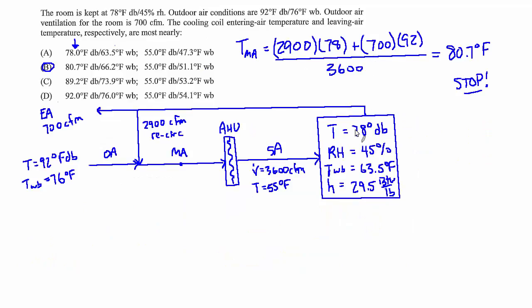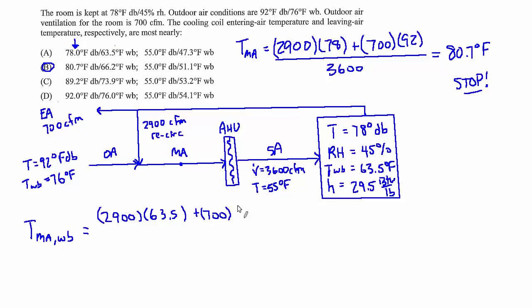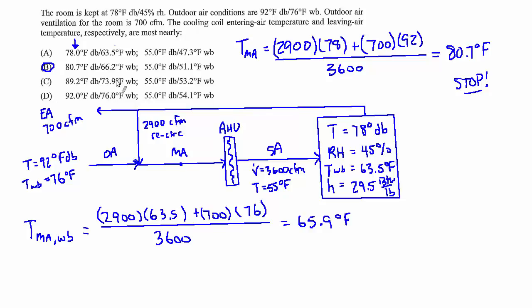We can do a similar mixing calculation using wet bulb temperatures: T_mixed_air_WB = (2,900 CFM × 63.5°F WB + 700 CFM × 76°F WB) ÷ 3,600 = 65.9 degrees Fahrenheit. This is very close to the answer choice value of 66.2°F. The small error comes from reading the wet bulb off the psych chart imprecisely, which is close enough and supports our answer.